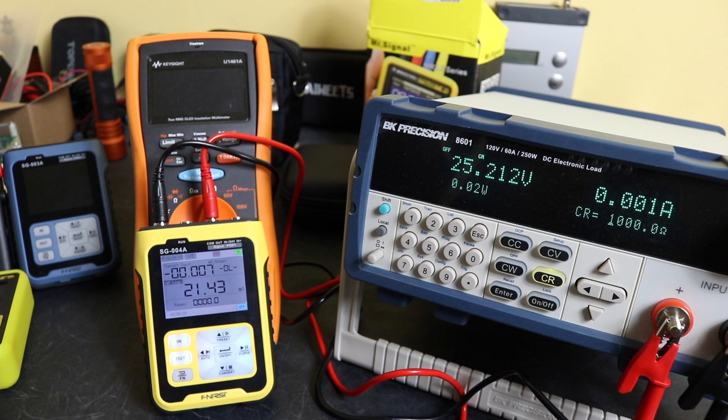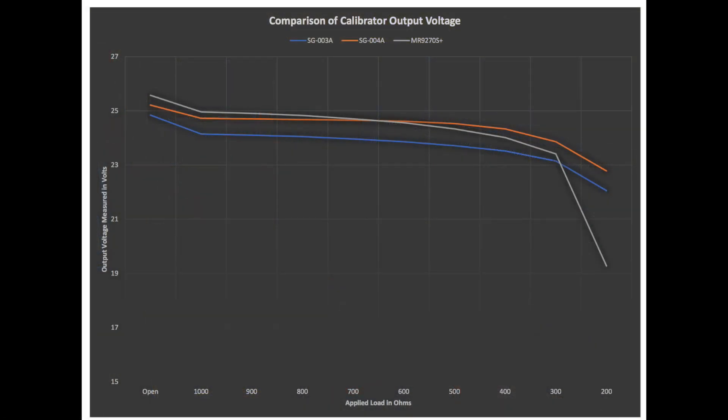Just for a change I'll put the results plot up. You can see these are the three curves produced from these units. The two FNIRSI units pretty much follow the same pattern as you'd expect, but you do see the output of the SG-003A slightly lower than the SG-004A. I believe that difference is more likely due to the condition of the batteries within the units rather than the electronics itself.